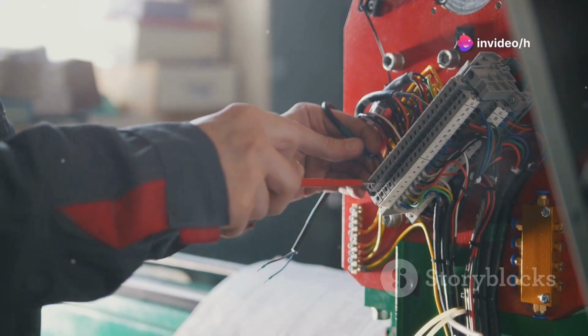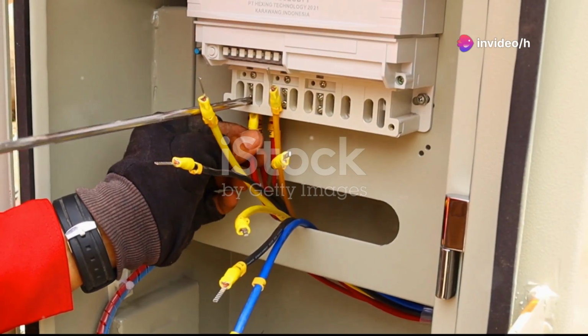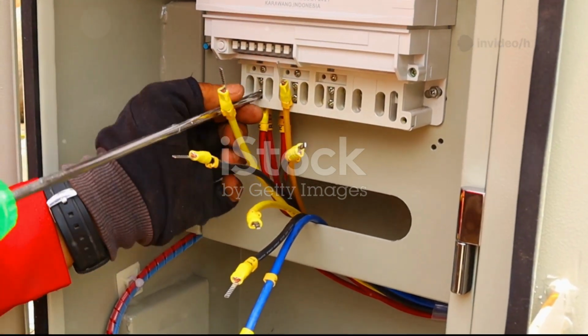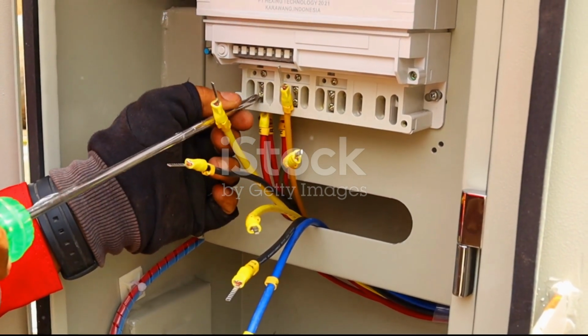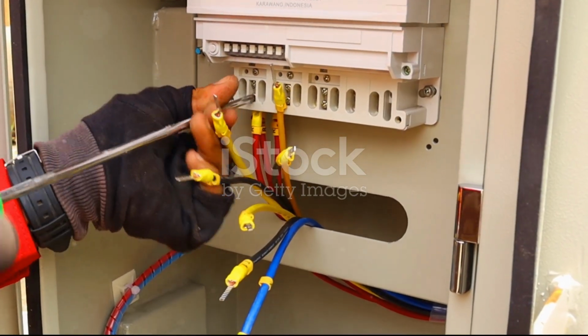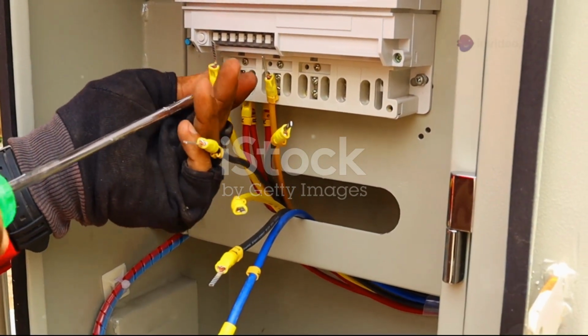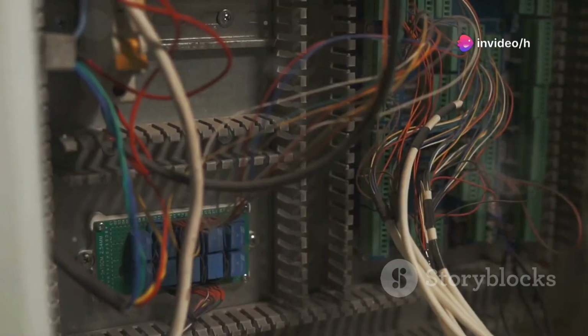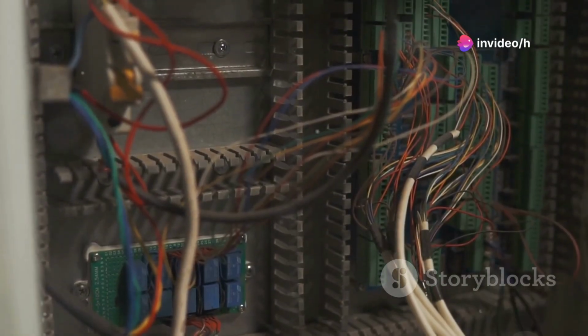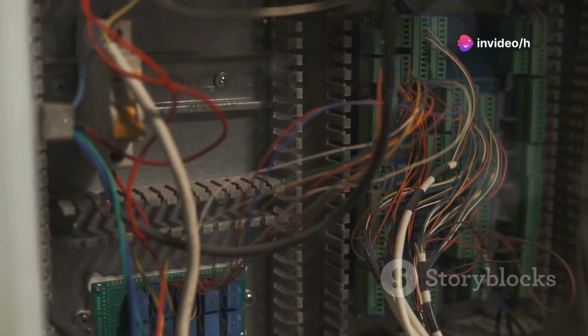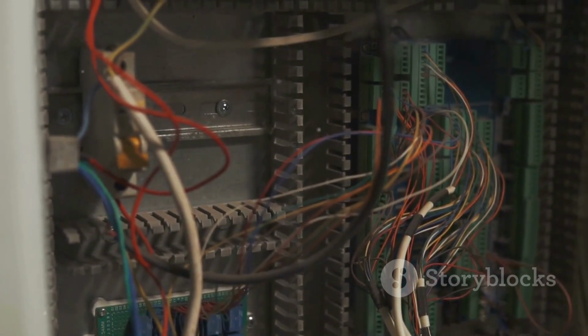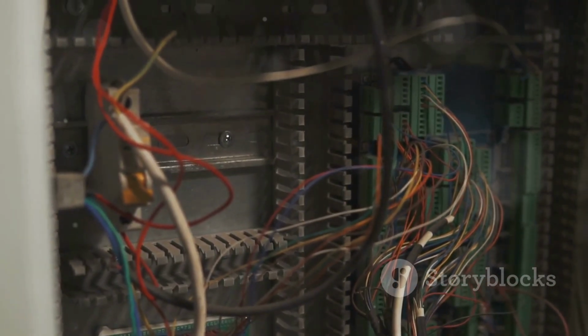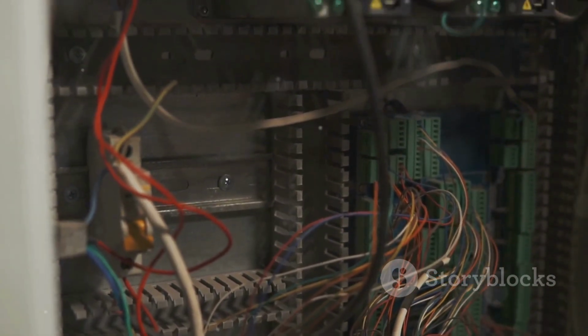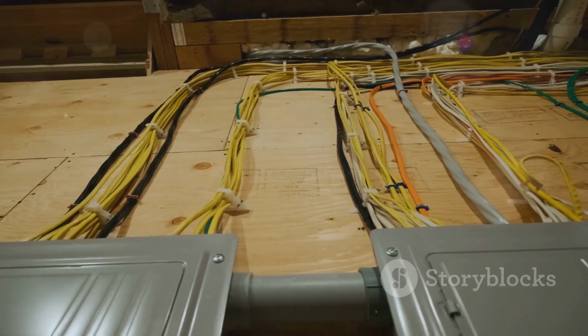Carefully measure the space inside your enclosure, cut the DIN rails to the correct length, and mount them straight and level. Precision here is crucial. Crooked rails can cause alignment issues and make future work much harder. Always leave deliberate gaps between components for airflow. Overcrowding your panel can lead to overheating, which not only shortens the lifespan of your equipment, but can also create dangerous conditions. Next, install wiring ducts.